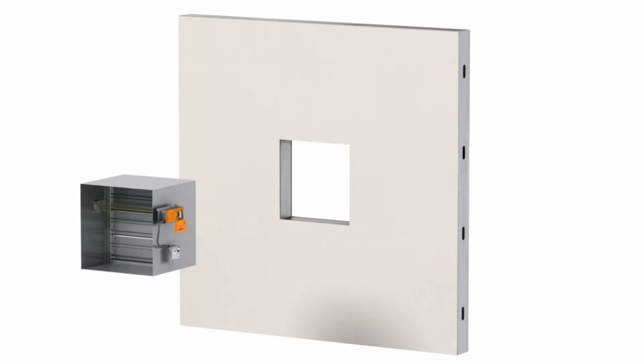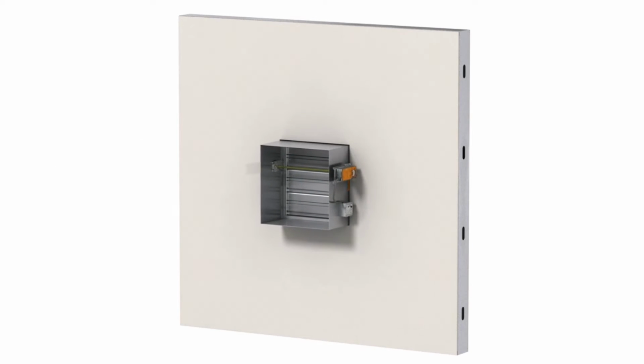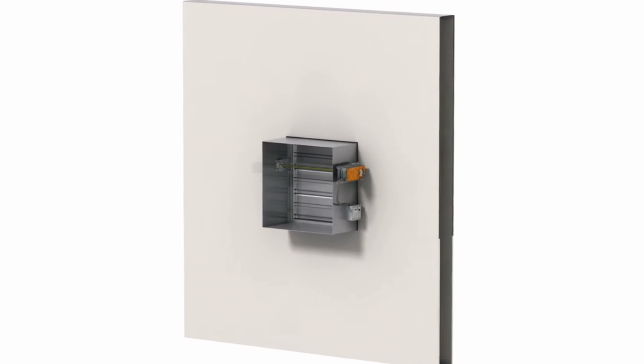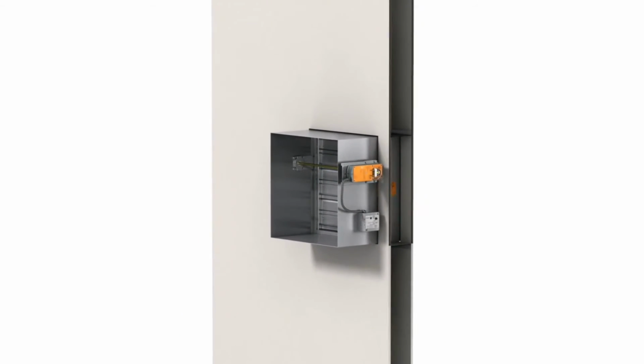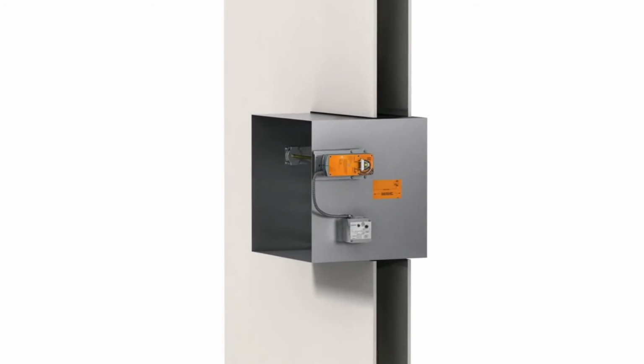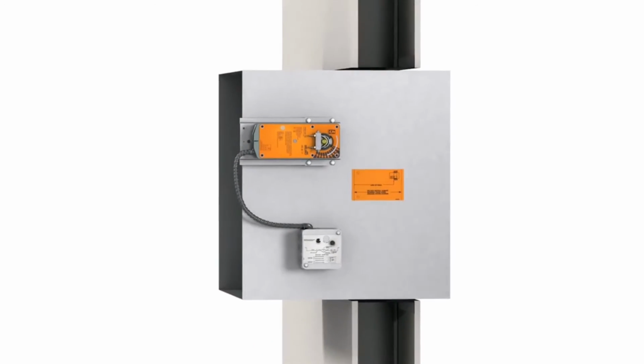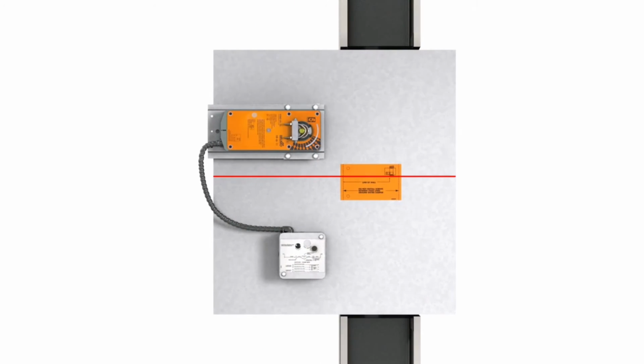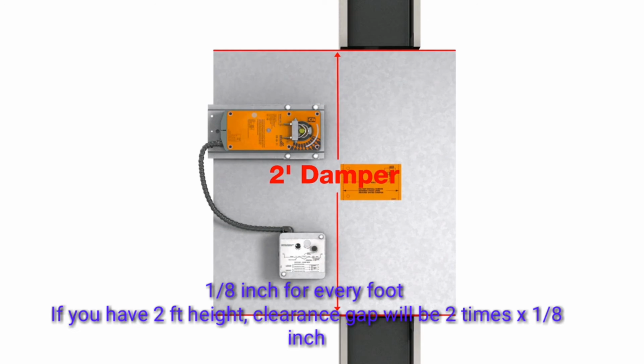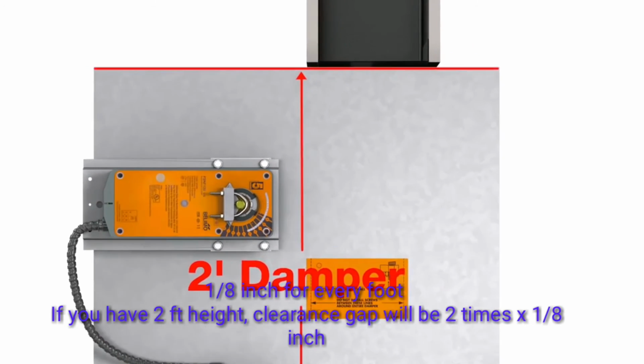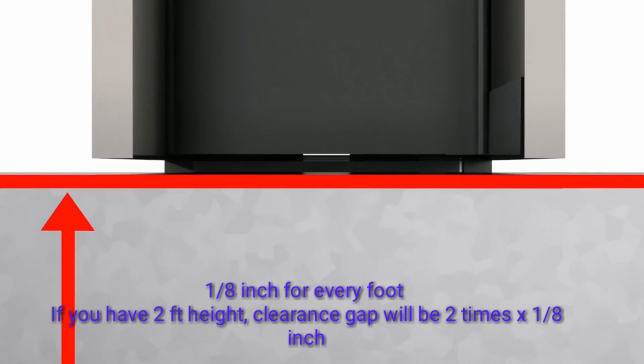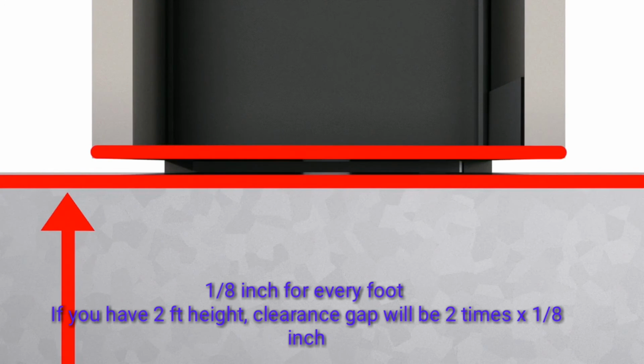A space between the damper sleeve and the wall is left to allow for the thermal expansion in the event of fire. Like you see here, the space is generally required to be 1/8 inch per linear foot of damper dimension but not less than 1/4 inch. As I mentioned, 1/8 inch clearance is required for every foot. If you have a 2 feet height damper, then the clearance gap will be 2 times 1/8 inch.